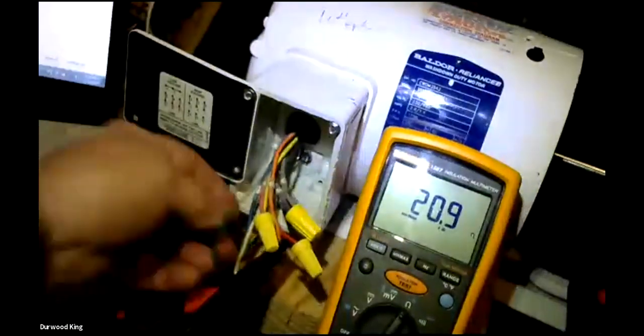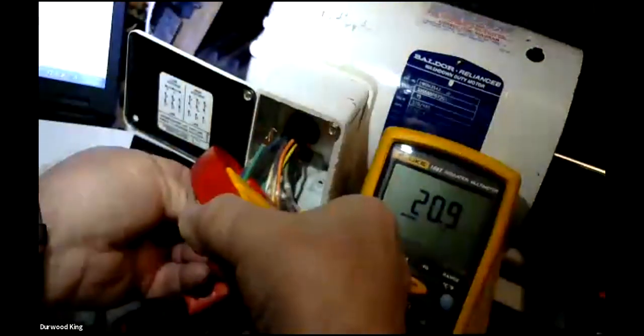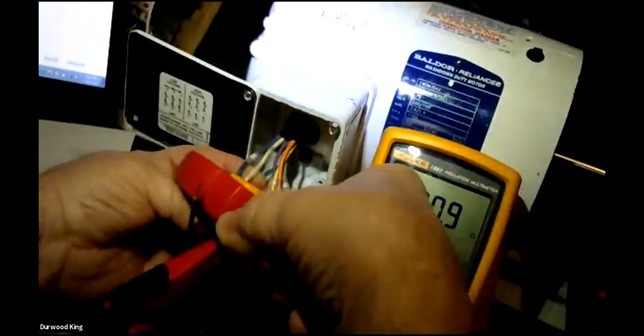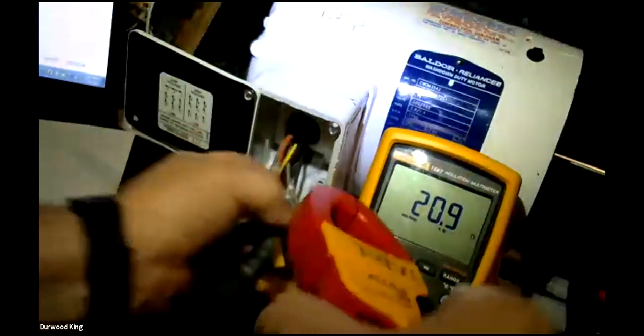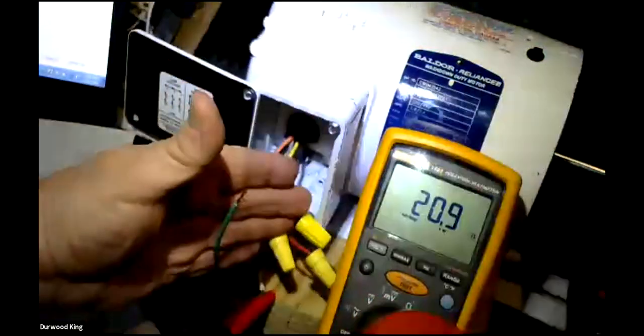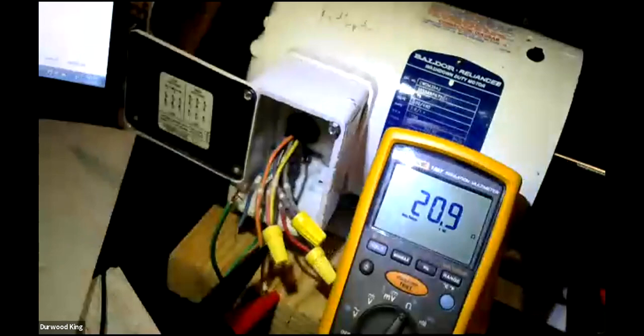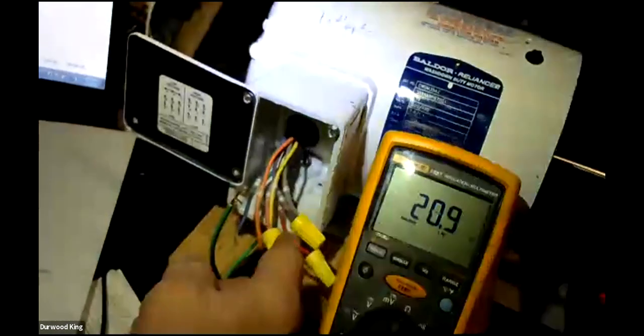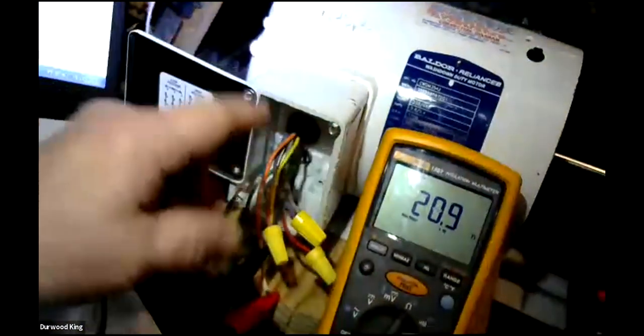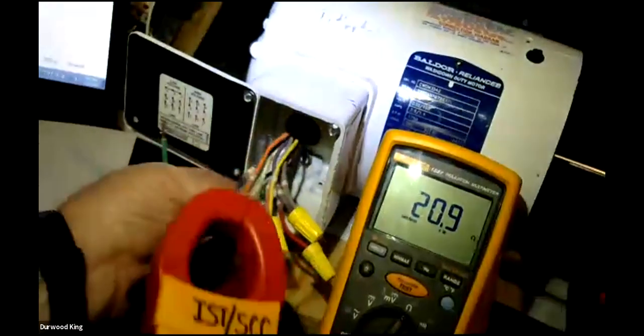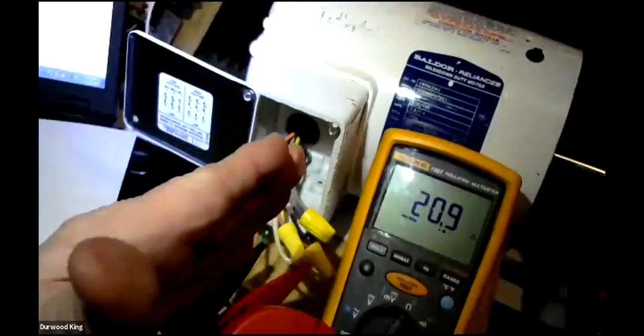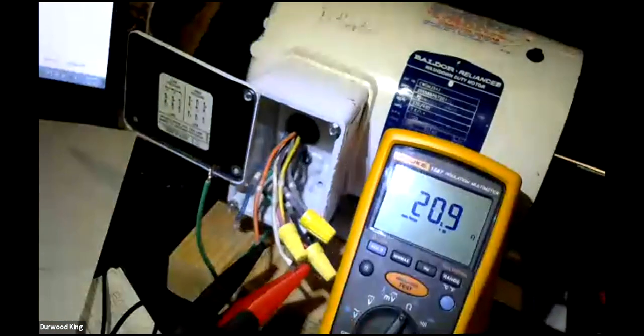So here's what it was. You check the amps on one leg, and you would be drawing amps. The next leg you're drawing amps, and the next leg isn't drawing any amps. You had higher amps on two legs and no amps on the third leg. So if you've got a broken winding in there, you're going to have an imbalance on current. It's not going to be the same amps per leg when you check those three. Two of them will be similar, higher than normal, and the other one won't have anything.